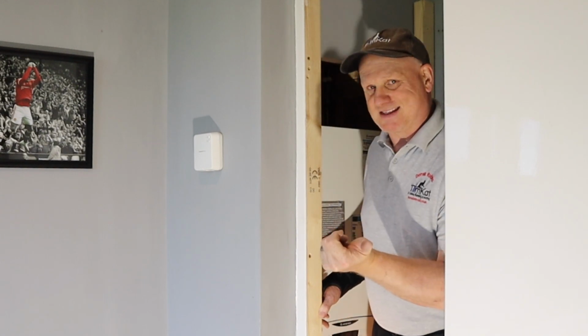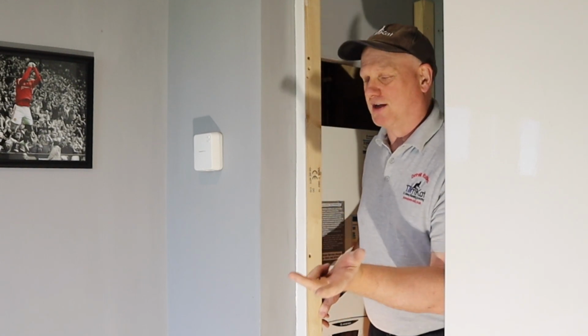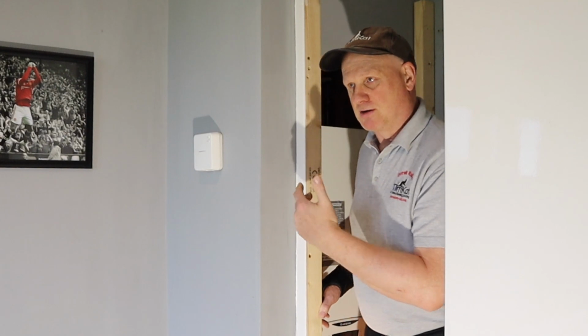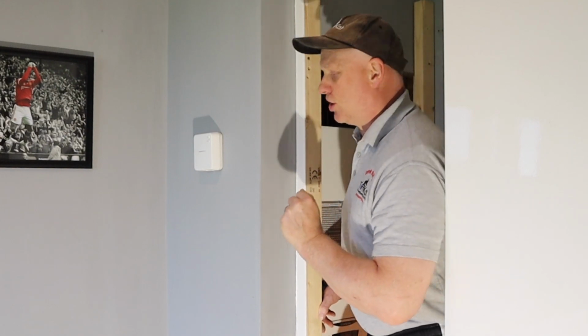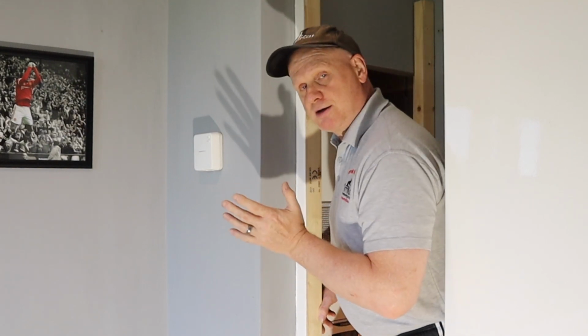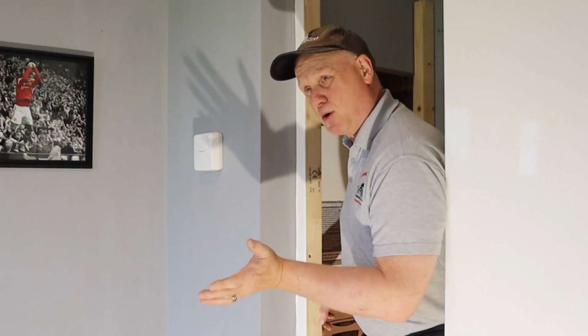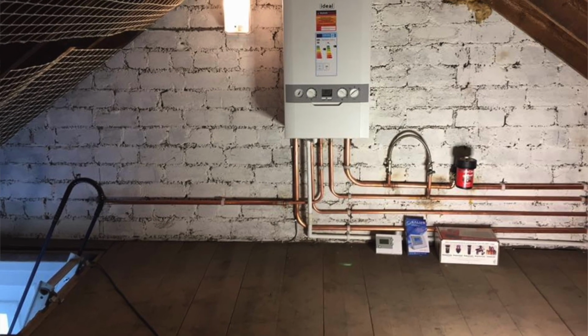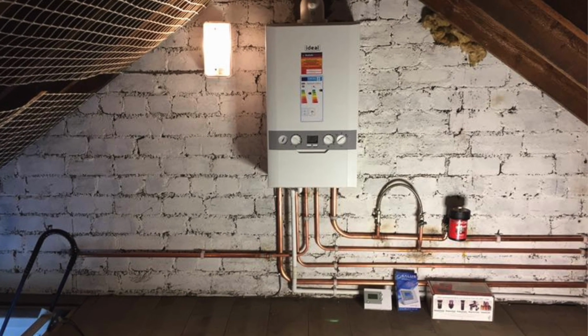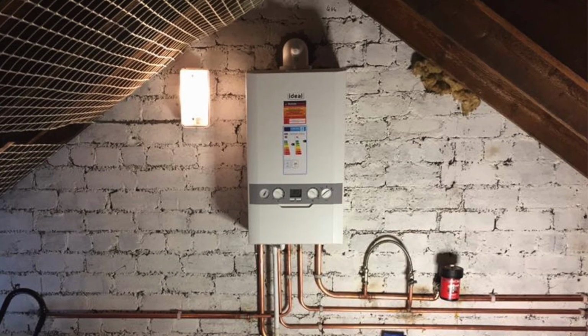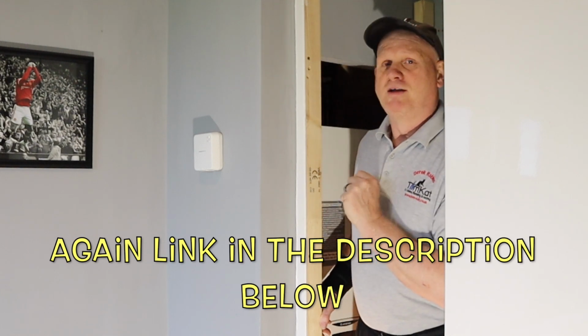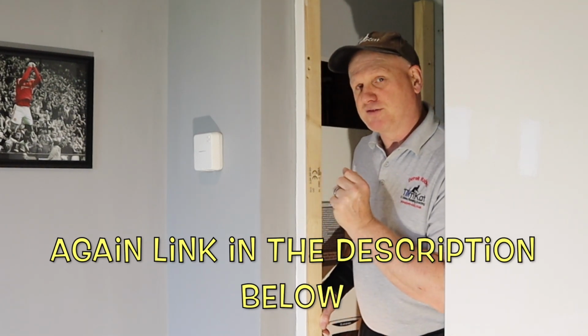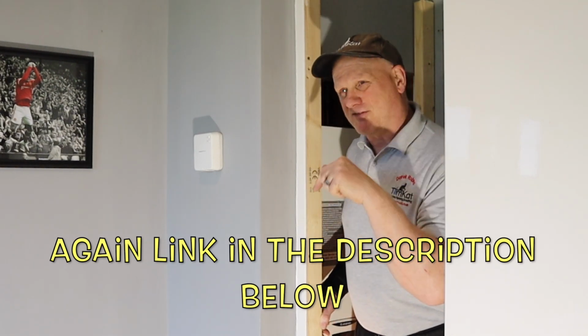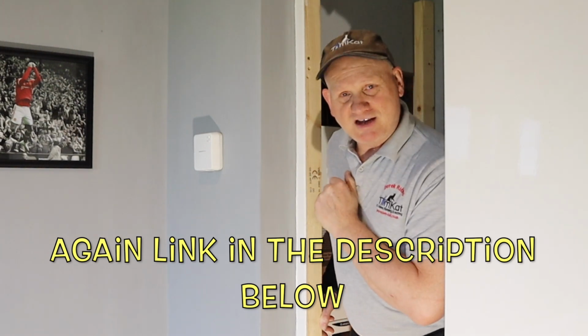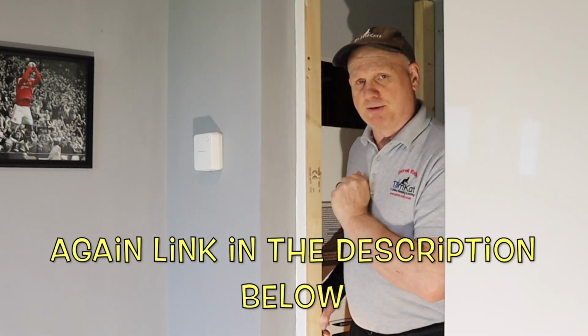Now we can isolate the gas, electrics and water outside this cupboard, so that was one of the things I did make sure I did. So gaining access to boilers is important. If your boiler is in a loft, it needs to have a fixed ladder, a permanent light, and a walkway all the way to the actual boiler. Now I've done a video on installing a boiler in a loft, and if you want to catch that video after you've watched this one, then I will leave a link in the description below.